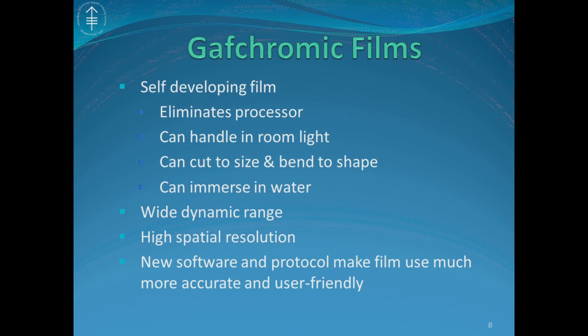As you all probably know already, radiochromic film is self-developing. Since it changes colors on exposure to ionizing radiation, it can be handled in room light, be cut to size, bent to shape, and can be immersed in water. The EBT3 film has a wide dynamic range from 2 centigray to 4,000 centigray. The spatial resolution can be up to 1,000 dpi. With the new software and protocol, the film dosimetry has become more accurate and user-friendly.